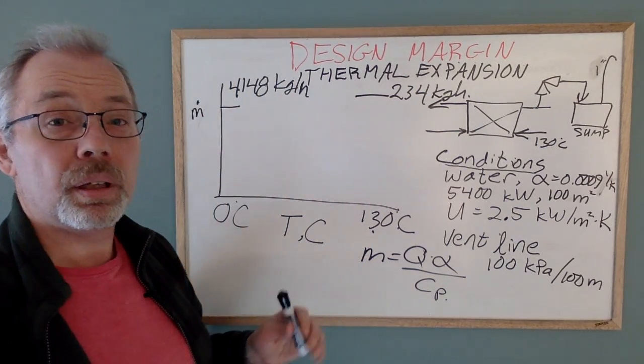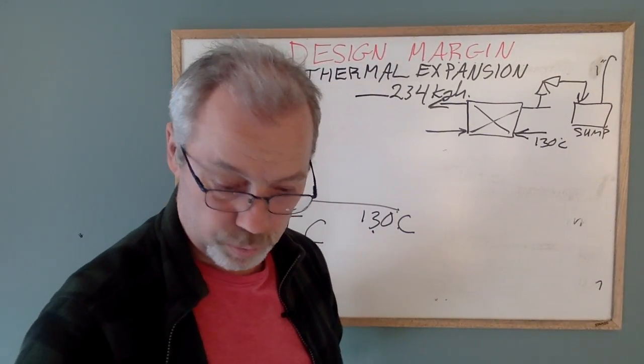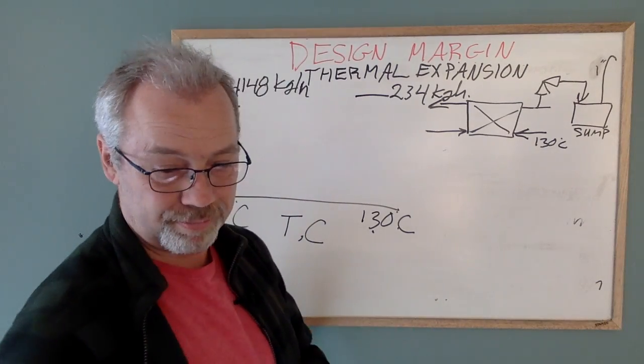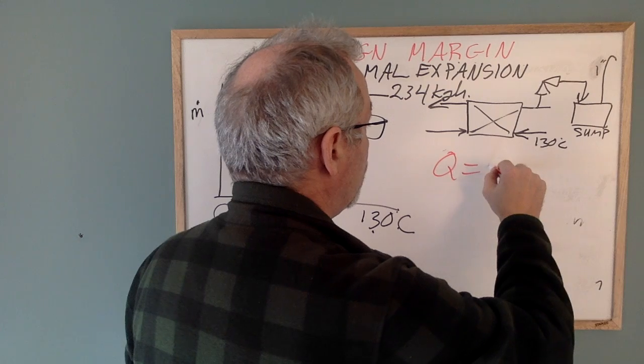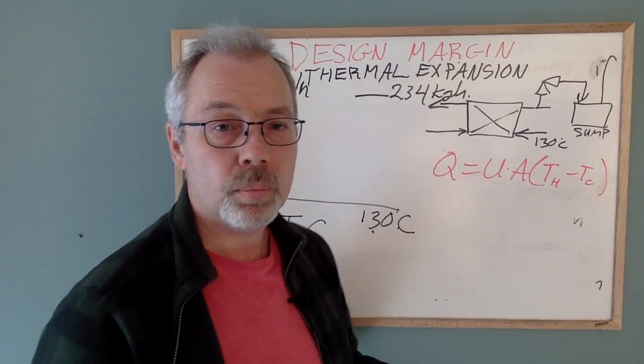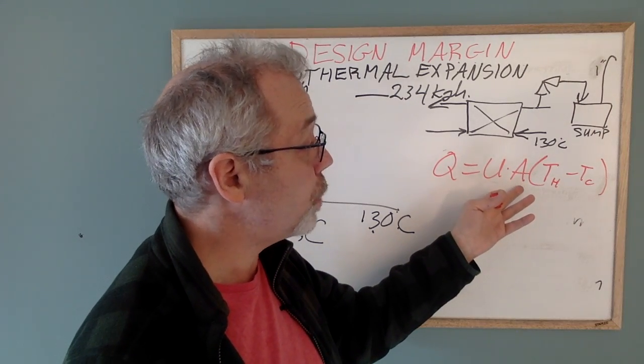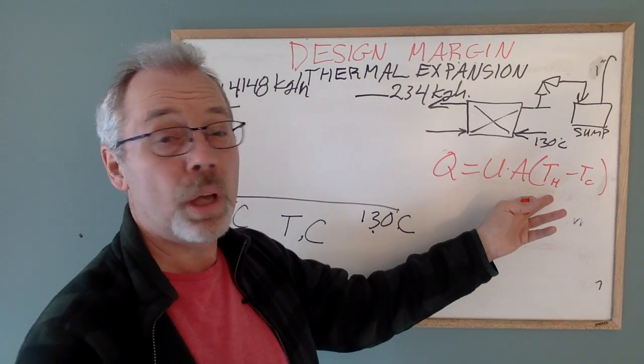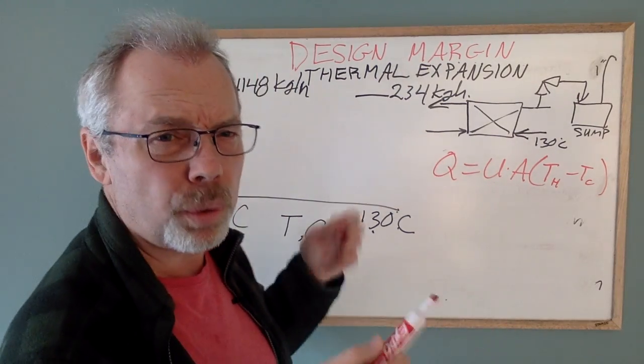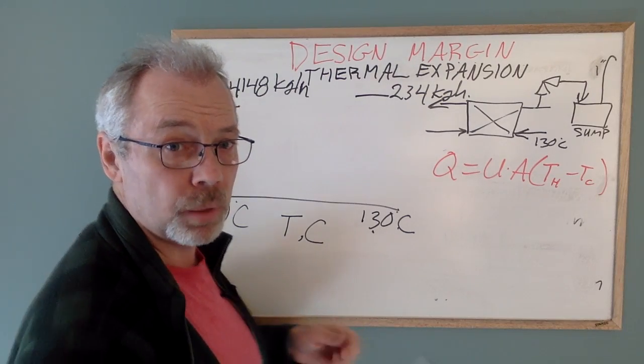So instead, let's approach this as a heat transfer problem. As a heat transfer problem, Q is equal to U A (T_hot minus T_cold). And in this case, we know what the heat transfer coefficient is. It's 2.5 kilowatts per meter squared Kelvin. 100 square meters for the area. The hot side is at 130 Celsius. And we'll let the cold side vary from 0 degrees up to 130 degrees. I won't do the math here. Check out my website, check out my blog. Look at the math for the relieving mass flow.